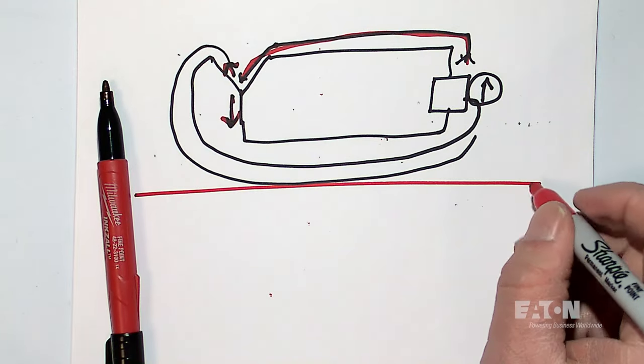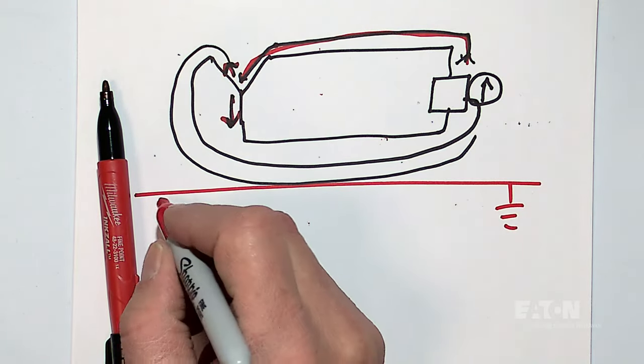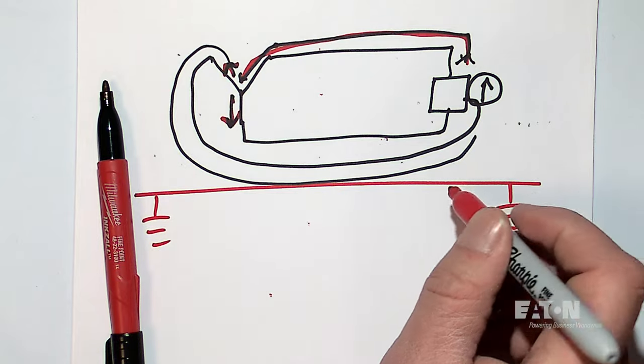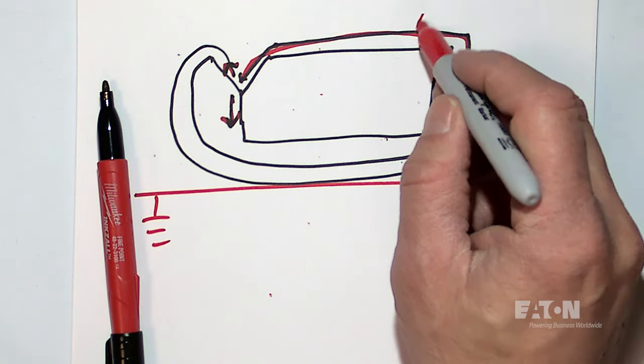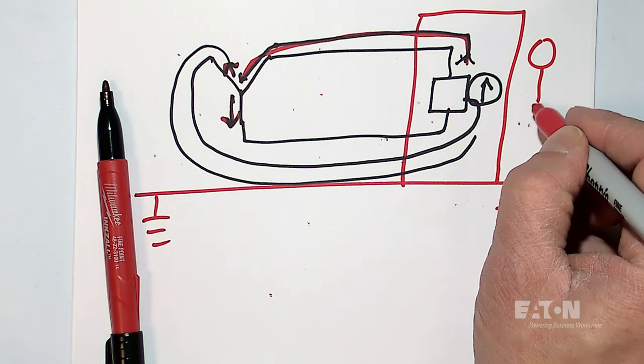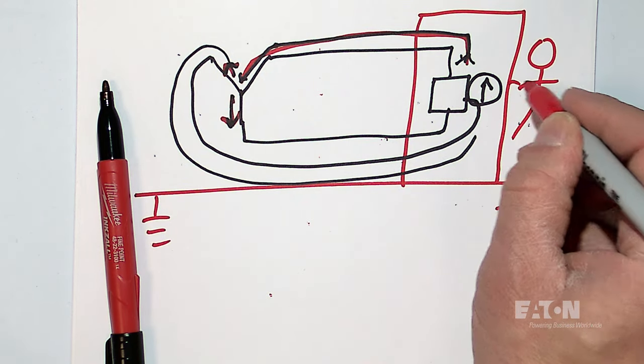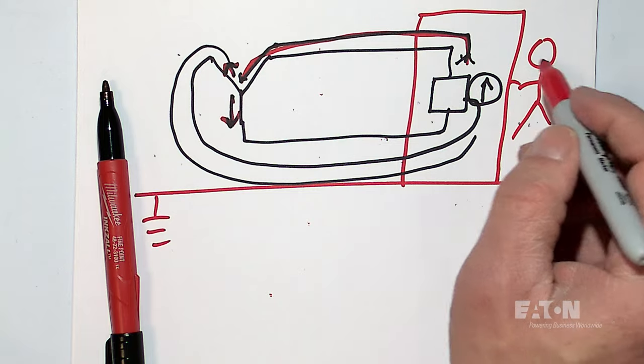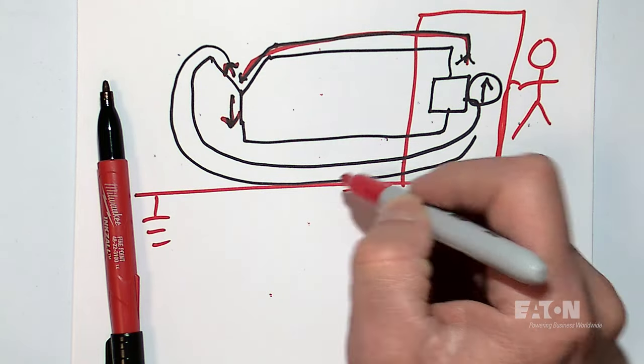the ground, my earth, my ground here, the only intention for that is to ground the metal components to the equipment, so that if somebody touches it, they're not going to get shocked, because then if there's a fault, current's going to want to flow back through that path.